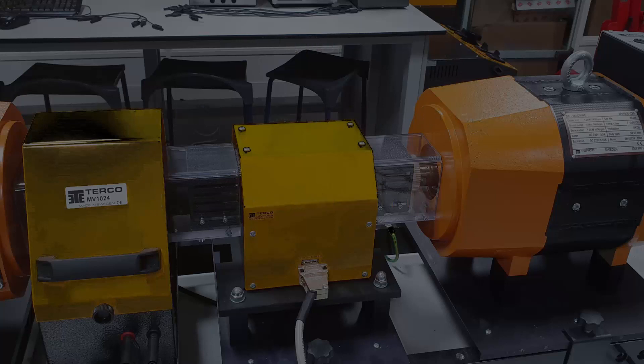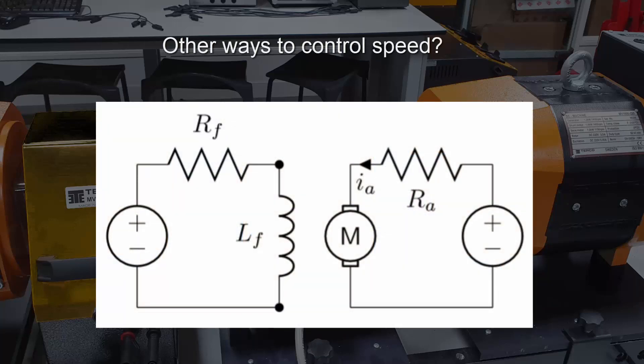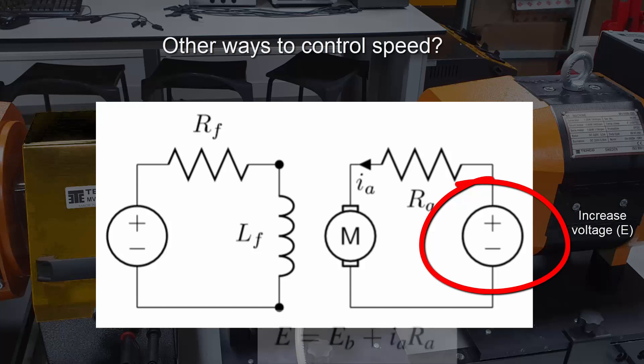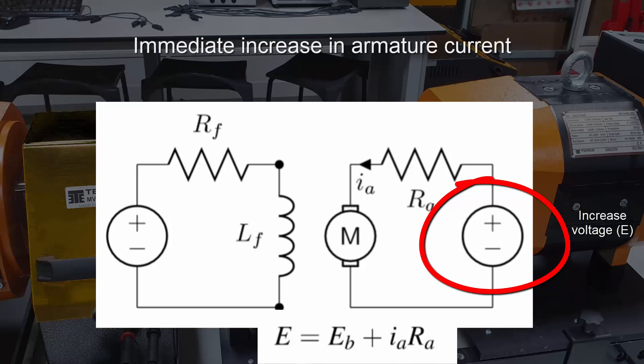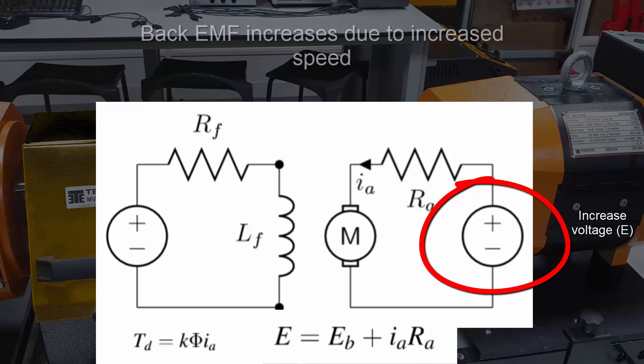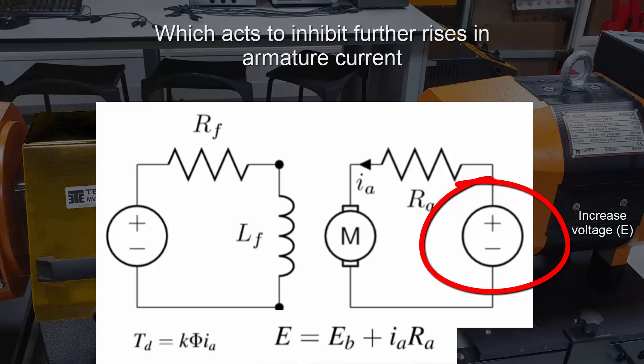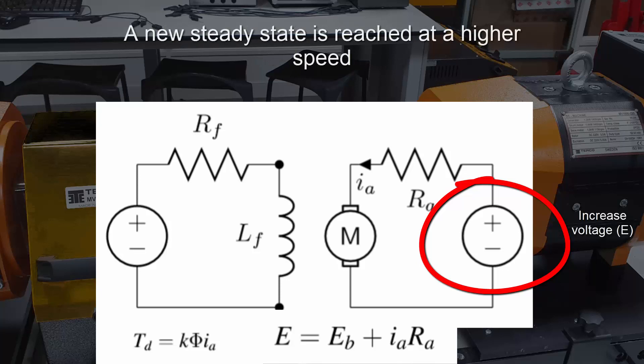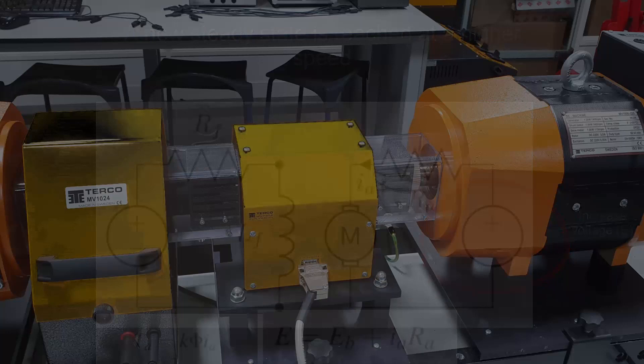Now are there any other ways that we can control the speed of the separately excited DC motor? What happens if we increase the supply voltage to the armature? Well, the back EMF will need to increase to maintain the balance in the equation. So when the supply voltage is increased, there will be an immediate increase in armature current, which will lead to an increase in torque. The increased torque will cause the motor to speed up, which will actually increase the back EMF. This reduces the current until a new steady state is reached, but that new steady state will be at a higher operating speed. So we can see now that the armature voltage is another way to control the speed of the motor.